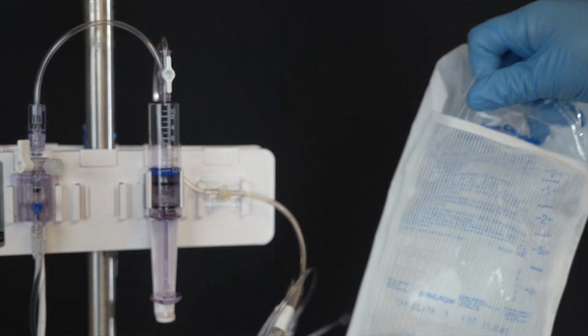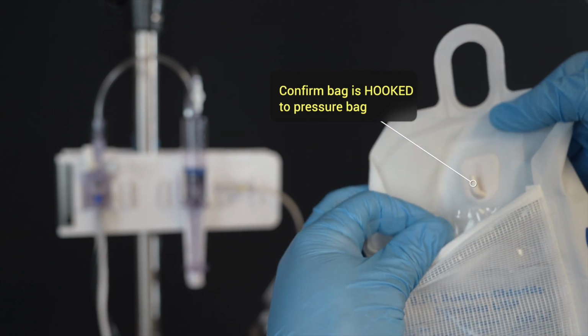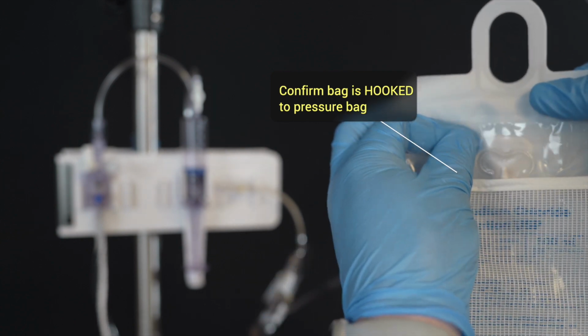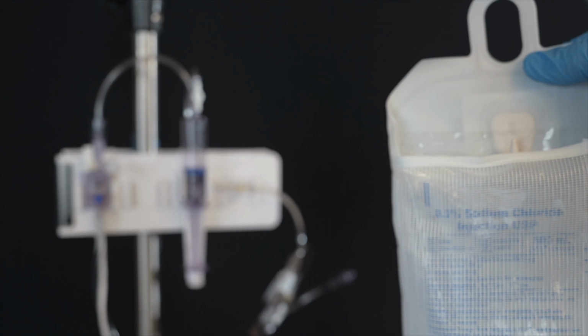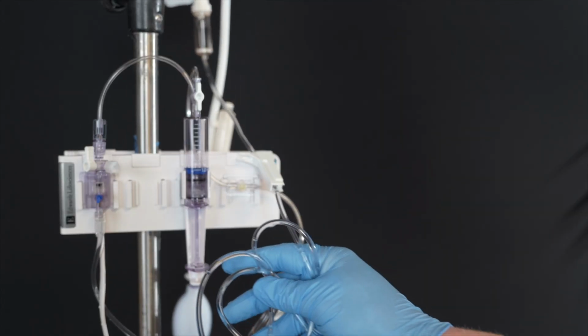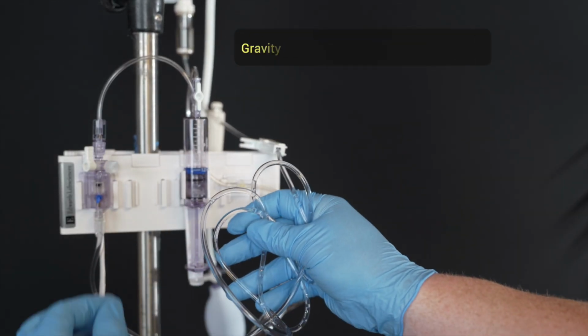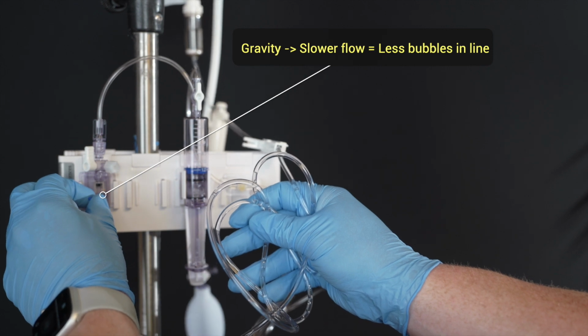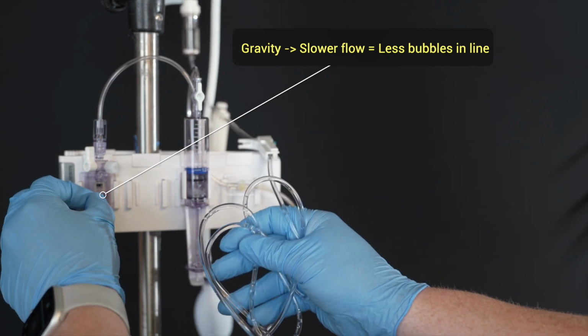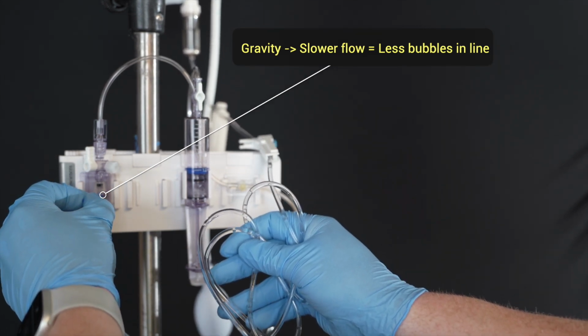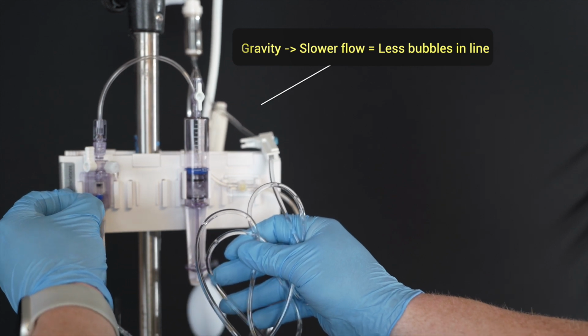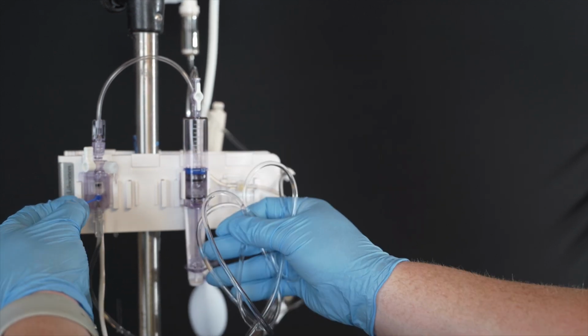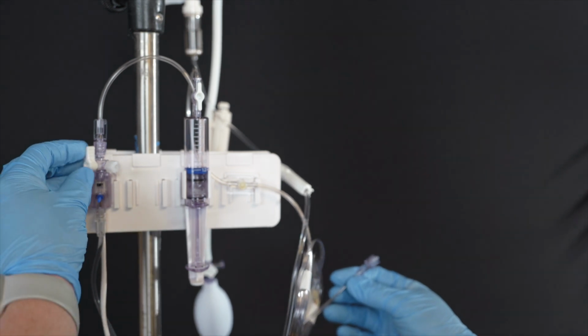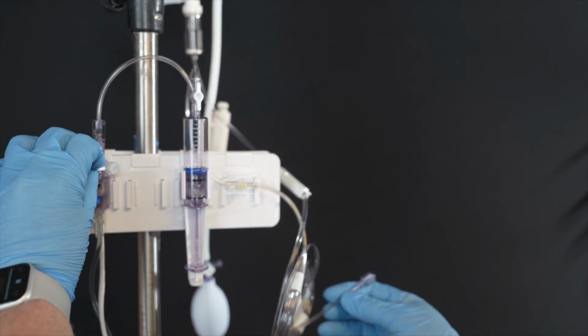Next, insert the IV bag into a pressure bag and hang it on an IV pole about 2 feet above the patient. Confirm the IV bag is securely hung on the IV pole. Next, prime the TrueWave system to gravity. Do this by pulling on the snap tab flush device to deliver the flush solution through the TrueWave transducer and out through the vent port's vented cap. Remove all air bubbles. Close the vent port by turning the stopcock toward the cap.